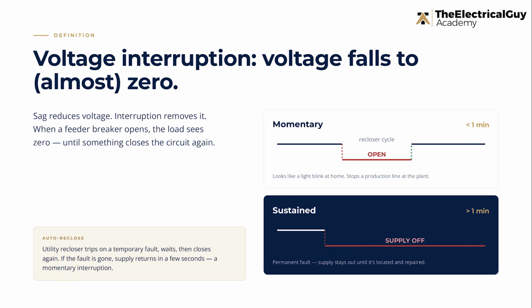There is a difference between these two. A momentary interruption can happen when a utility system clears a temporary fault. For example, a tree branch touches an overhead line, creates a fault, and the protection system trips the feeder. After a short delay, the recloser closes again. If the fault is cleared, supply is restored. From the customer side, this may appear as a short power cut of 1 or 2 seconds maybe. For a home user, this may just look like a blink of the light, that's all. But for an industrial user, this may stop an entire process.